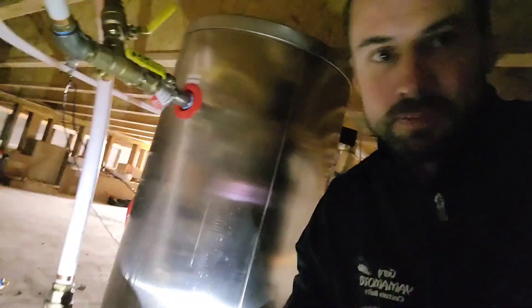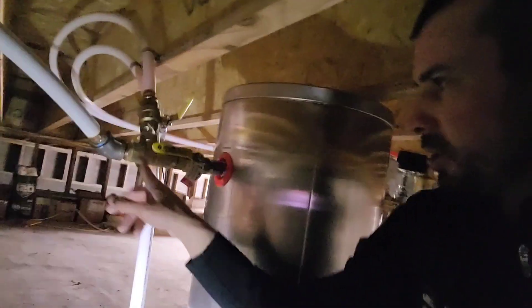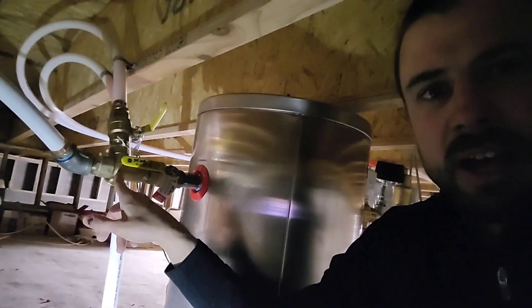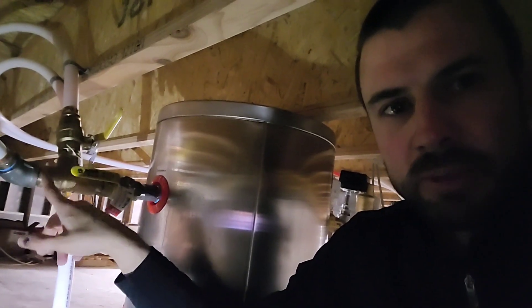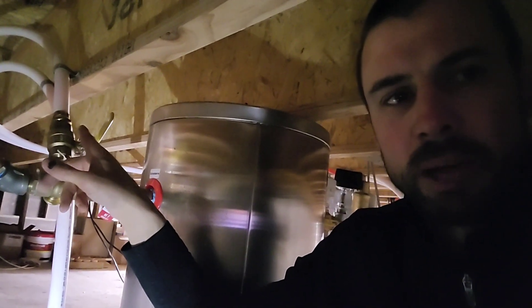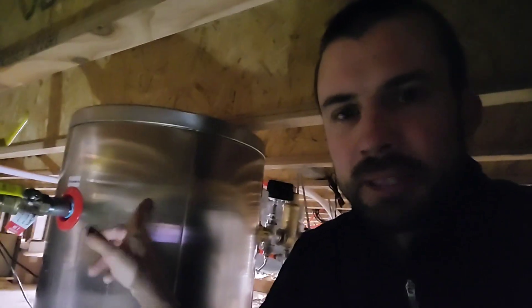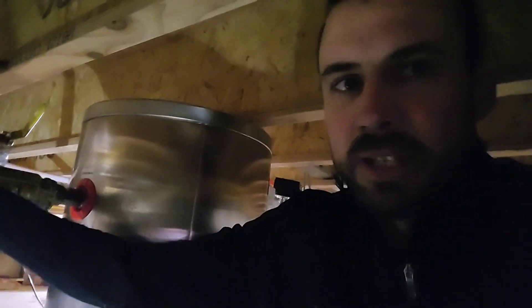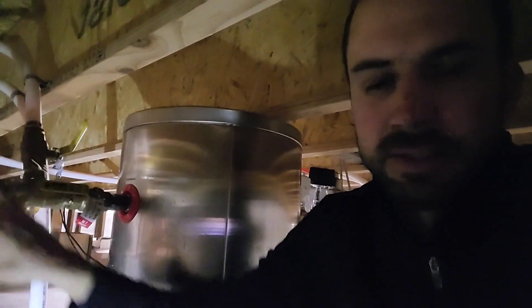The spin-down filter keeps the system clean. We have another air separator, and then on the return side we have a mixing valve that goes to my hub, which allows the ChilTrix system to preheat water in my hot water heater or fully heat it. Then of course it comes into the buffer tank. Right now it's running into the buffer tank and this pipe is about 80 degrees, as we saw.